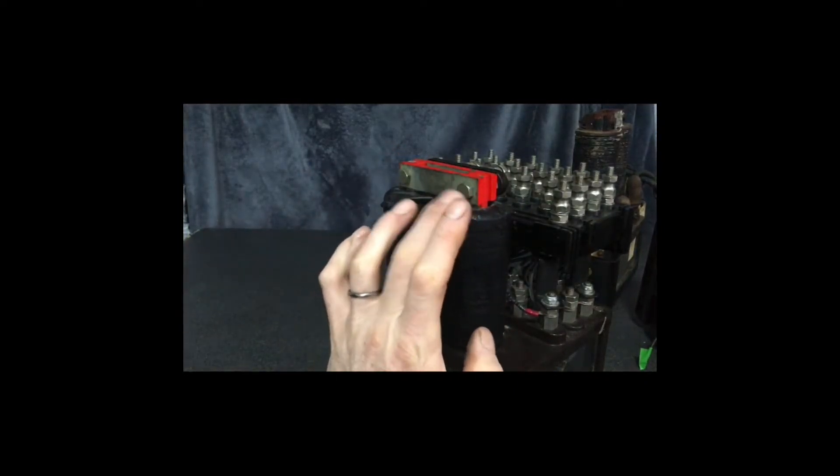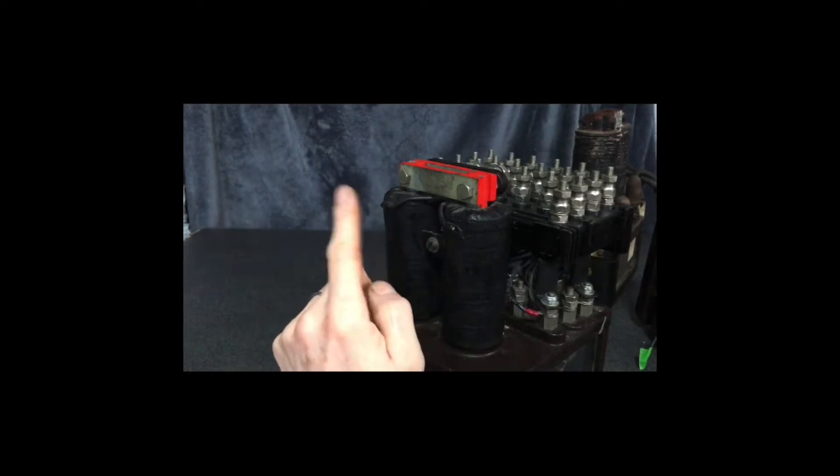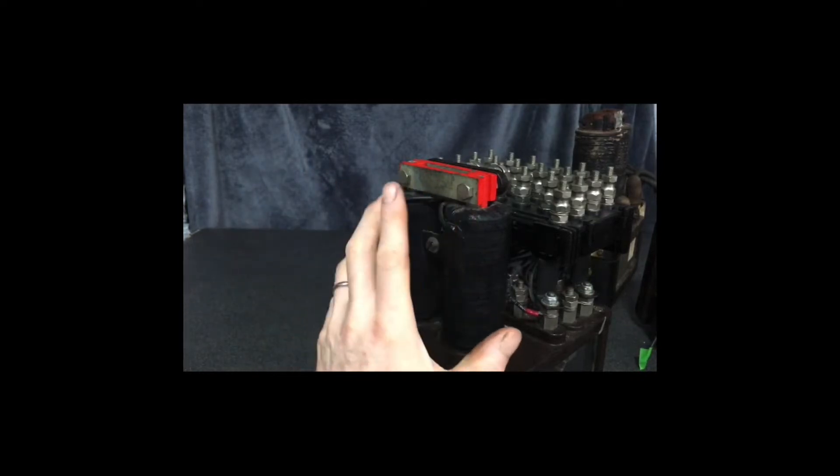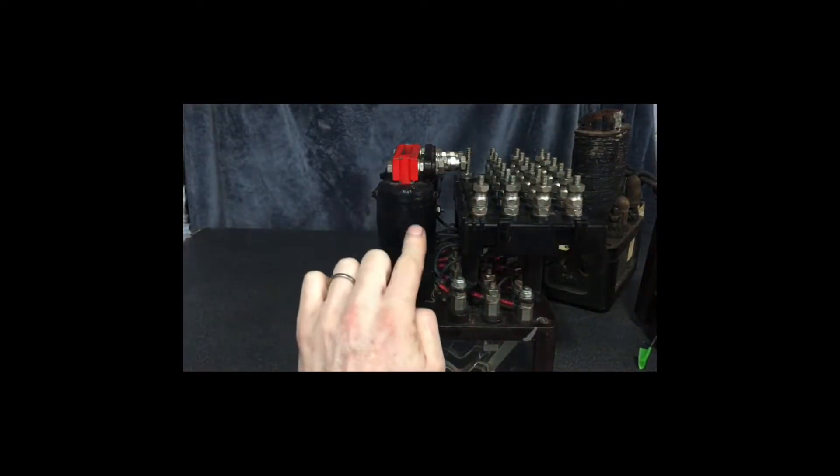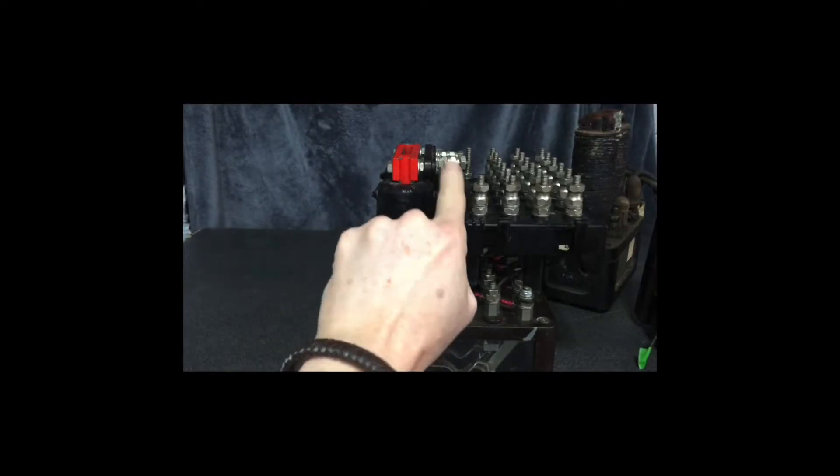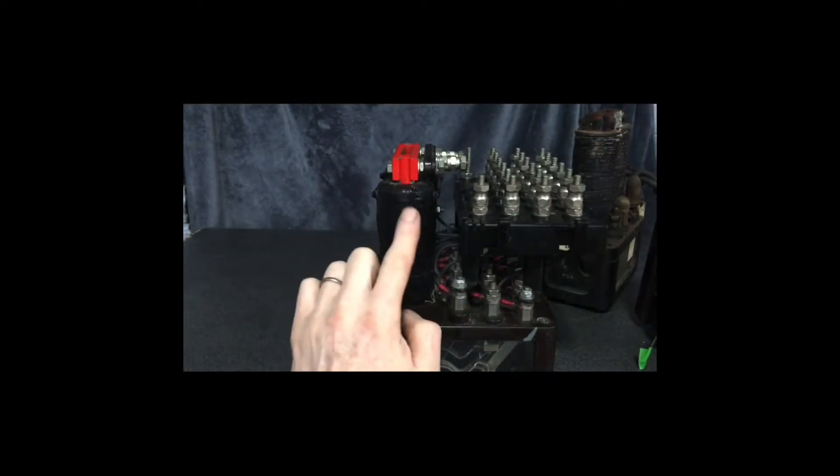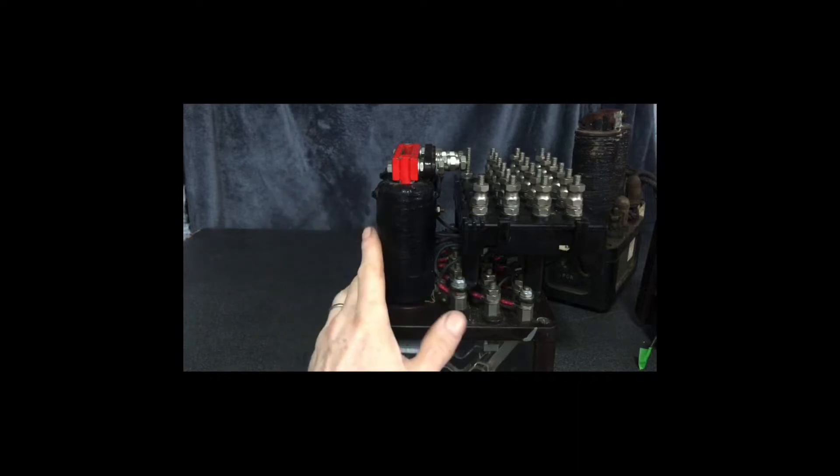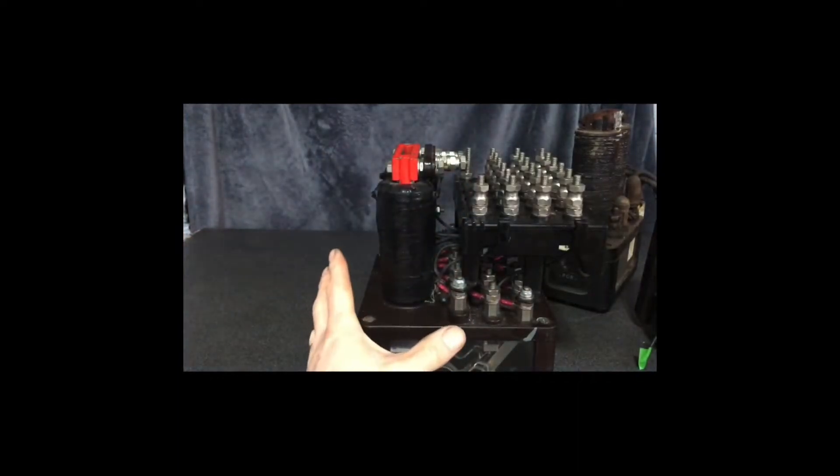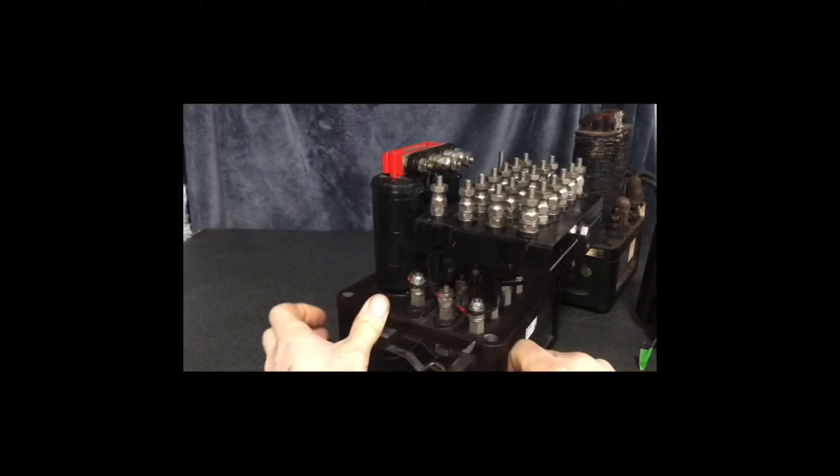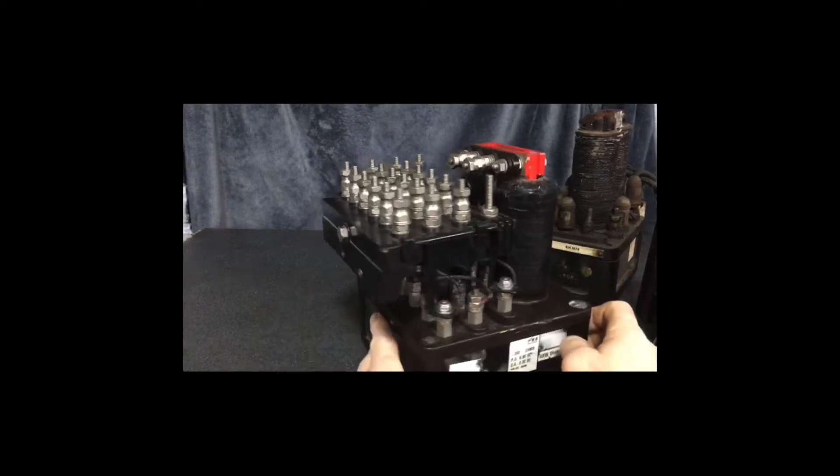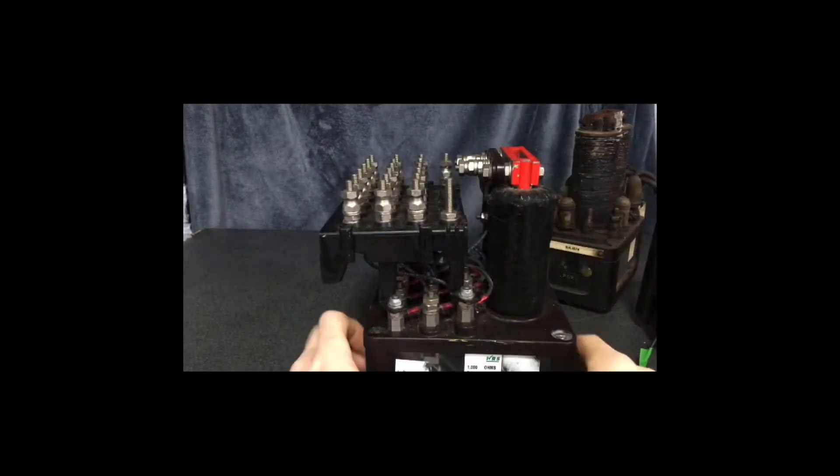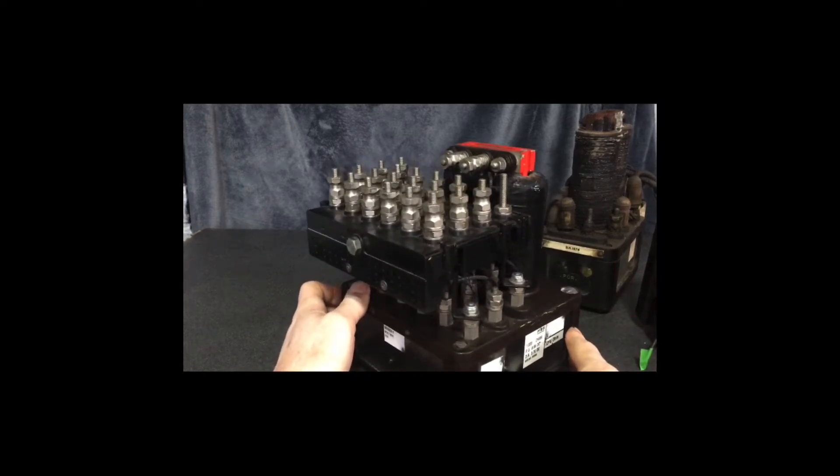They are capable of working on one coil. If one coil fails, it is capable of working on one coil. An old trick that they used to do, we don't do anymore, but if a coil failed you would strap out that center terminal to pass the failed coil and it would work. Now on line relays, this relay which I'll explain in a minute, that's probably quite fine. On track relays it does affect the operation. That's one of the old get outs they used to do when relays failed because these are worth quite a lot of money to get replaced. You obviously want to keep it in service as long as possible.